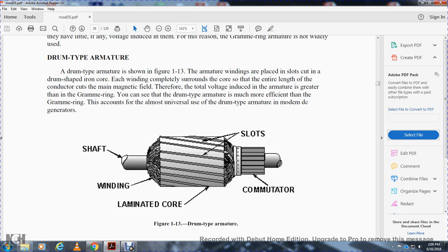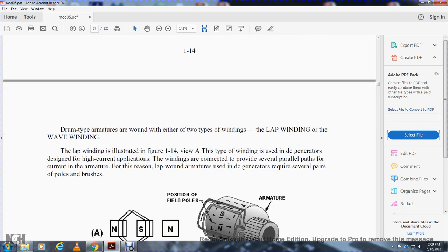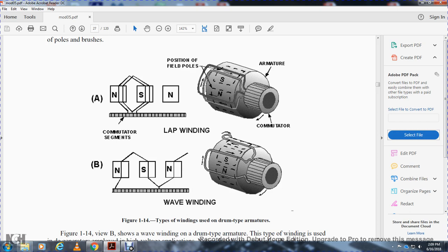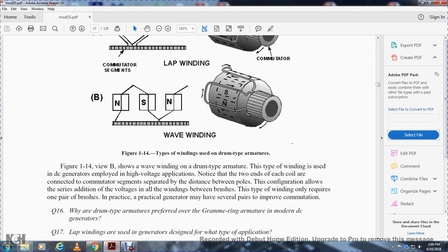The drum type armature has a shaft, winding, laminated core with slots, and commutator. Drum type armatures are wound with either of two types of windings: lap winding or wave winding. Lap winding, illustrated in figure 1-14 view A, is used in DC generators for high-current applications. The windings provide several parallel current paths through the armature, so lap-wound armatures require several pairs of poles and brushes. Wave winding, shown in figure 1-14 view B, is used in DC generators for high-voltage applications. The two ends of each coil are connected to commutator segments separated by a distance equal to the pole pitch, allowing voltages in all windings between brushes to add in series. Wave winding requires only one pair of brushes, although additional pairs may be added to improve commutation.